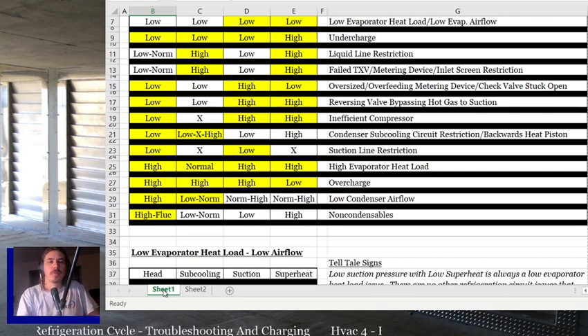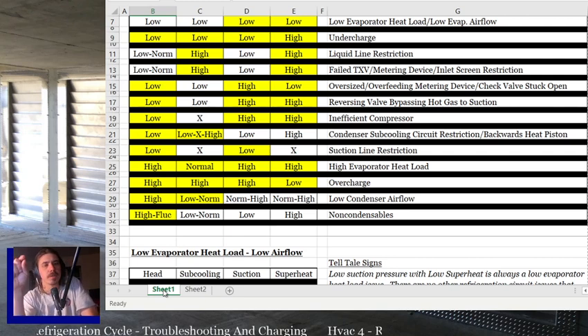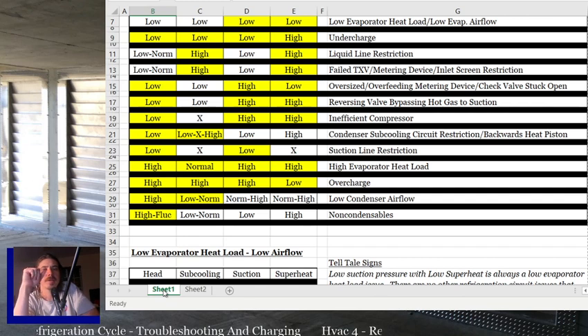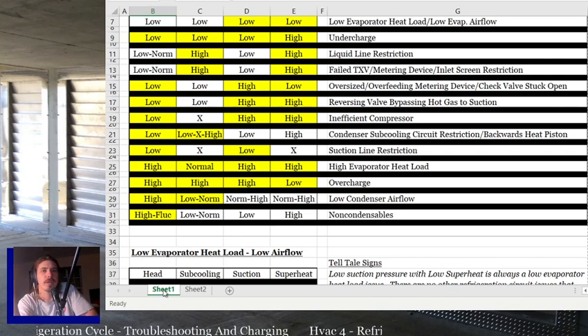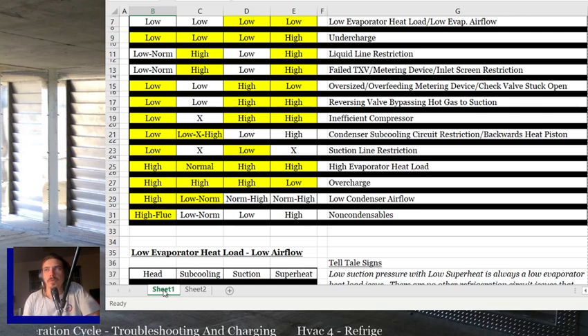Infrared thermometer will help you find non-condensables if they're stuck in the condenser, because where the refrigerant's not traveling in the condenser, it'll be the same temperature as outside ambient. Looking for circuit restrictions, you'll see the cold section, or you'll see the warm section in the evaporator if refrigerant's not feeding through a couple of those circuits inside the coil itself. Other than that, they're just not common problems, so I don't think it's that important to throw them in here. If you run into those, you're going to have fun figuring it out anyway, because you're probably going to suspect one or two things first.